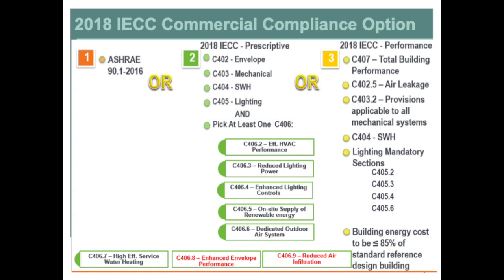So as far as compliance, we've got a few different options for commercial. Predominantly we see most people use IECC, either prescriptive or performance, with performance being an energy model. This is not ComCheck — ComCheck is actually a prescriptive compliance method. Or the IECC allows you to use ASHRAE 90.1. Robert noted controlled receptacles, which is generally one of the reasons people don't like 90.1. So we see mostly IECC, either prescriptive or performance, for compliance.